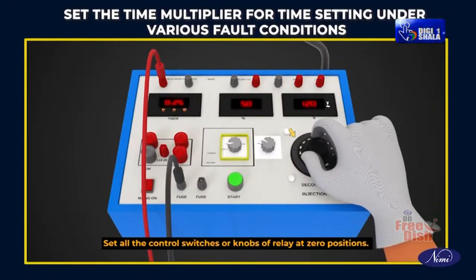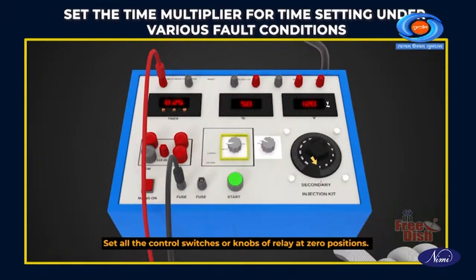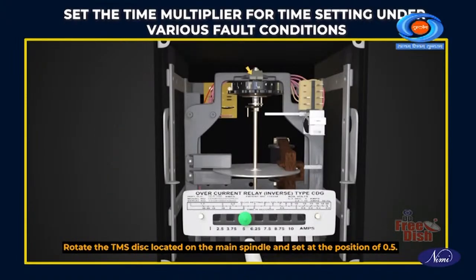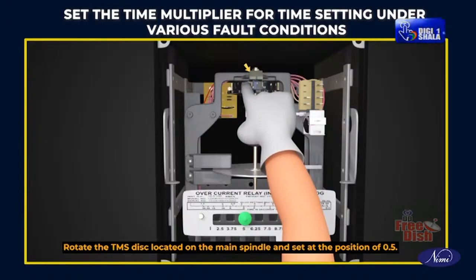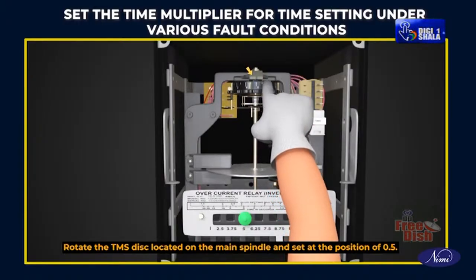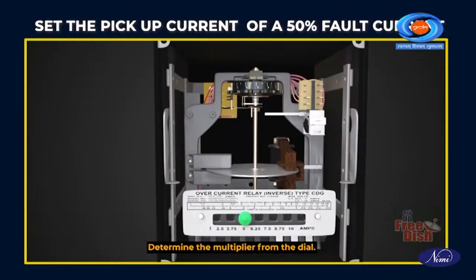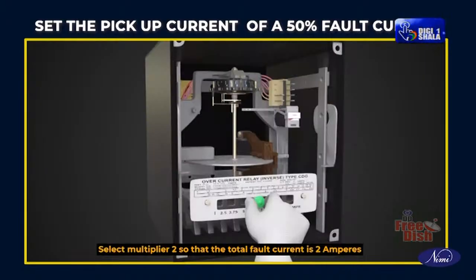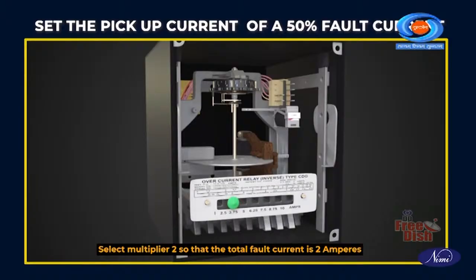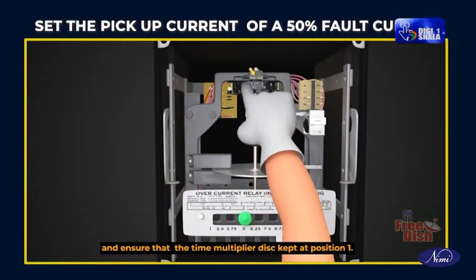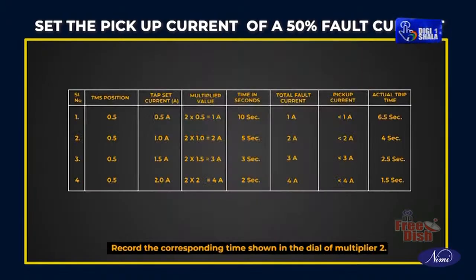Set all the control switches or knobs of the relay at 0 positions. Rotate the TMS disc located on the main spindle and set it at the position of 0.5. Determine the multiplier from the dial. Note down the values. Select multiplier 2 so that the total fault current is 2 amperes, and ensure that the time multiplier disc is kept at position 1. Record the corresponding time shown in the dial of multiplier 2.